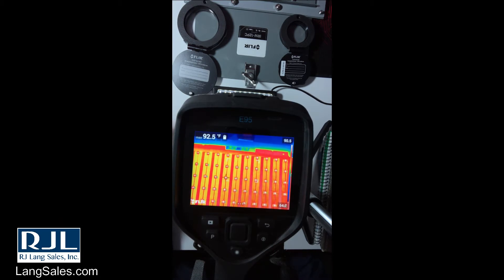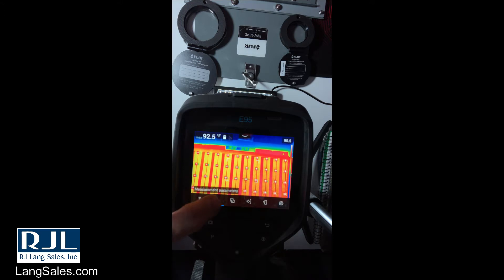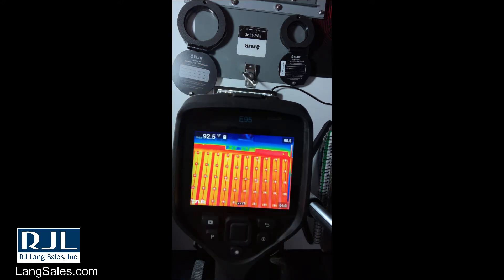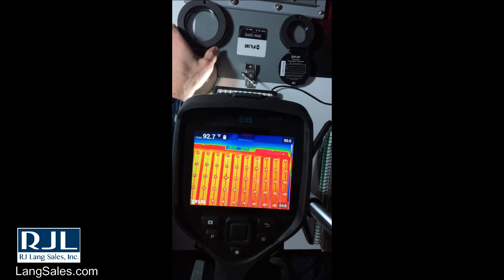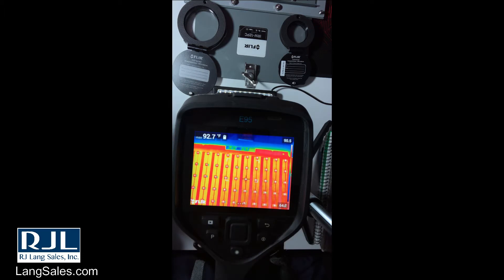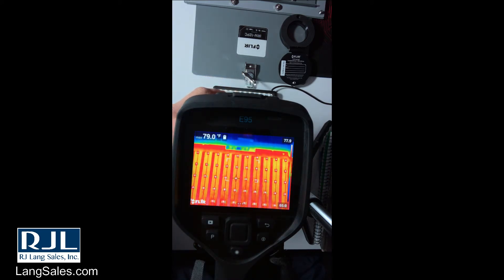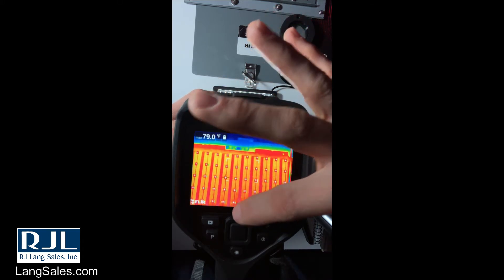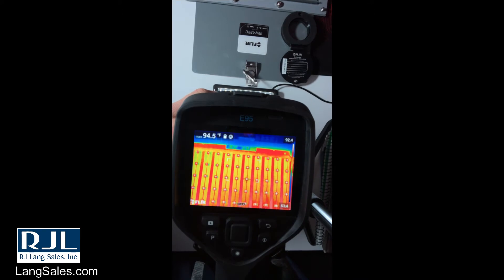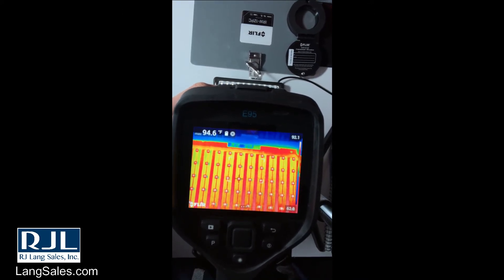But what was that transmission percentage? So what I'm going to do is turn off the infrared window compensation. As you can see here, it's jumping around between 92 and 97 degrees. When I put the window in front of it, it's down to 78 to 79 degrees. But if I turn the infrared window compensation on at 40% transmission, we're up at 94 degrees.